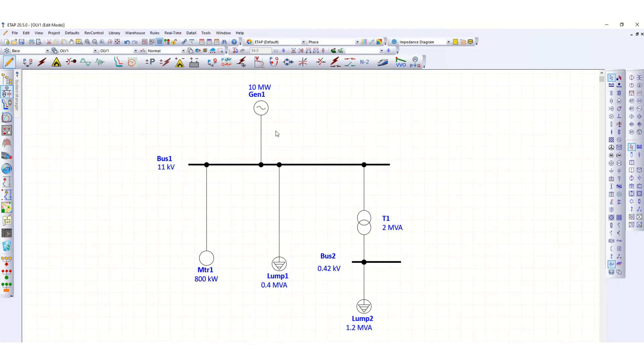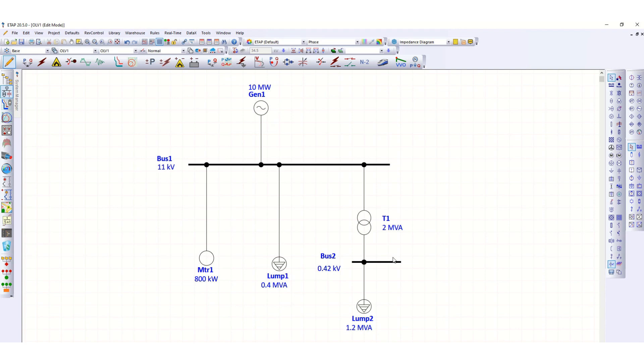During load flow analysis using ETAP software, you can find that in some cases your bus is under voltage. How to get rid of this issue? I will discuss here. One thing you can do always is reduce the loads connected to the bus.